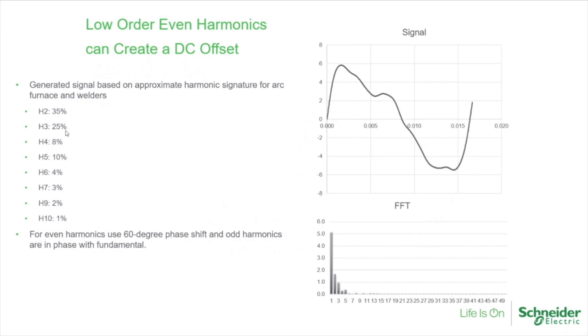And then some other notes on harmonics. The even harmonics are usually out of phase with your fundamental, and it's usually between the phases. So I just use a 60-degree phase shift for reference, but it'll actually be different. Your odd harmonics aren't going to be in unity. They might vary a little bit, and same with your even harmonics. They're not typically in phase with your fundamental wave shapes. But in this example, you can see how the zero crossing has been offset, and it's not the same on the top and bottom.